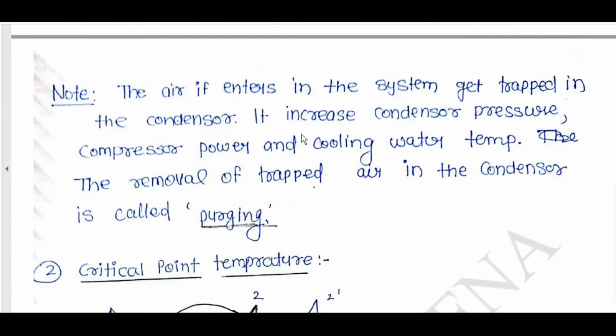The air, if it enters the system, gets trapped in the condenser. It increases condenser pressure, compressor power and cooling water temperature. The removal of trapped air in the condenser is called purging.